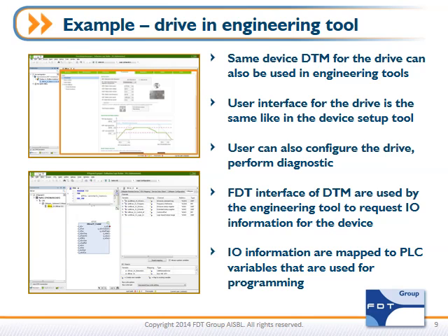We can take a more complex environment — such as an engineering tool for programming a PLC — and use that same device DTM for the drive within it. The user interface for the drive is exactly the same as in the setup tool, since it's supplied by the DTM. The user can configure the drive and perform the same diagnostics as in the standalone environment. But because this is an engineering tool, it also needs information such as the IO mapping for the device. That IO information then becomes mapped to variables in the PLC, used for the programming environment, as shown in the lower left picture.